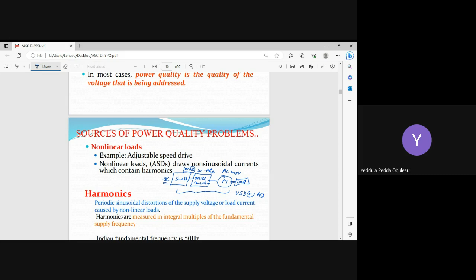When we treat this adjustable speed drive, which has the motor plus this power converter as main components, how does the operation of the motor impact the utility power supply that is connected? When it is connected to this drive, it will also impact the other loads connected to the same supply. When this motor is drawing the load current, because of its operation, at the supply side where more than one load is connected, other than our adjustable speed drives, harmonics are injected into the supply system. So to eliminate those harmonics, we'll be discussing what remedies are available.